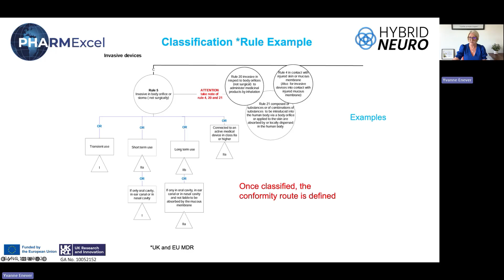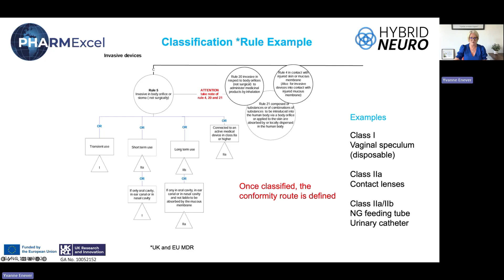To give you some examples, if you're looking at a vaginal speculum, for instance, that will be a class 1. These are products that you can self-declare, as we mentioned before. You don't necessarily have to go through the conformity assessment route. But then you've got things like contact lenses, or NG feeding tubes, that can be class 2A, or it could be a class 2A or 2B, depending upon your intended use. So being really familiar with the rules under the regulations is critically important to not being in a situation where you have misclassified your device. Once you've classified your device, that really sets your conformity assessment route. As we said before, class 1s don't necessarily need to go down that route unless they have a measuring or a sterile function, but your class 2s, 2As, 2Bs, or your class 3s will invariably involve a conformity assessment route.